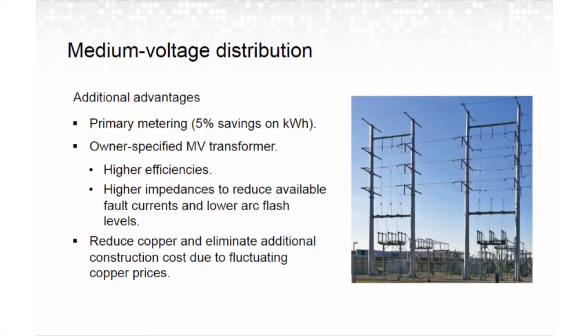Now, in addition to heat loss with medium voltage, there are other advantages of using medium voltage distribution systems, and I'll turn it over to Rich, and he can talk about them. Thanks, Ken. So, larger buildings or campuses have the option of distributing at higher voltages. Typical medium voltages include 4,160, 12,470, 13,200, and 13,800. Now, when we speak of those terms, we'll typically just abbreviate to 4160, 12.47, 13.2, or 13.8. And in that case, we're really kind of talking about kV.